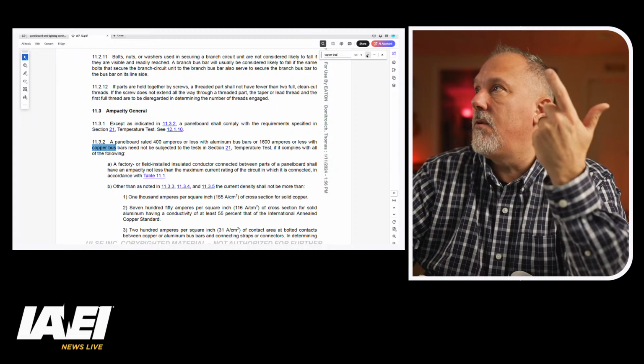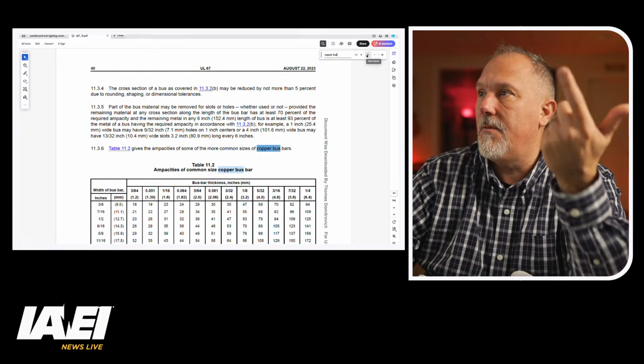I know there's something in here for 100% rated for a copper bus, and I cannot for the life of me find it. But in any case, somewhere in the standard, maybe it's in UL 489, I'd have to double check UL 489. But in any case, let me search here with Control F. Whoops, I have to hit OK. Because I don't have the right keyboard, I end up clicking the wrong stuff. All right. Sorry, everybody.